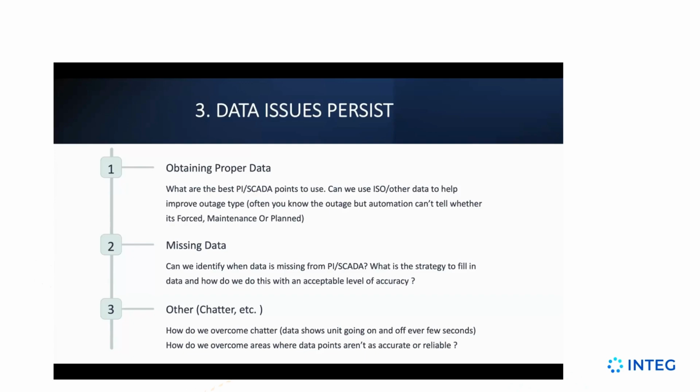If you have large chunks missing, what we do is we create information only events and say, hey, there was a comms failure or something. Then a human has to look into it and try to fill it in. And what gap constitutes that, each company can have their own comfort level. Certain companies are going to say, hey, listen, if there's more than an hour missing, then document it and we'll figure it out. And then we have the ability for them to add in manual inverter or turbine outages as well in the system. So keep that in mind.